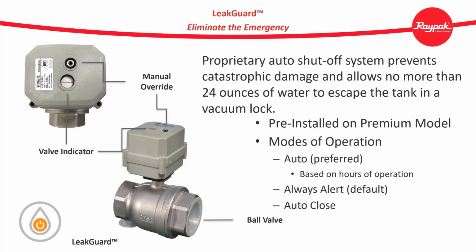In auto mode, the response is based on hours of operation. If a leak is detected during operating hours, it will alarm but not shut off the heater. If a leak is detected during non-operation hours, it will alarm, shut off the valve, and will also shut off the gas, so it is completely disabling the heater.